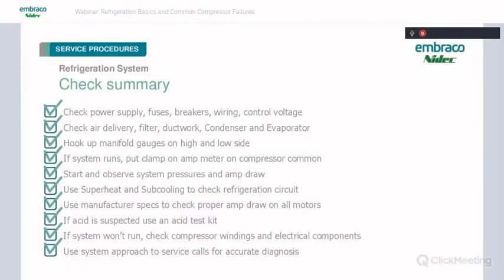So this is just a little refrigeration check summary. This is kind of something I used to do when I was in the field. It's a good place to start with the power supply. Check the fuses, breakers, the wiring, and the control voltage. I always like to start there because I may have started changing out a thermostat one time before I ever found out there was a bad fuse. But anyway, then go to your air delivery, check your filter, your ductwork, your condenser and evaporator, make sure they're clean. Go ahead and hook up your manifold on the high and the low side.